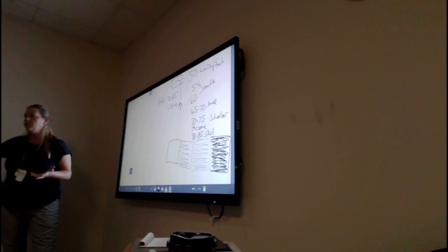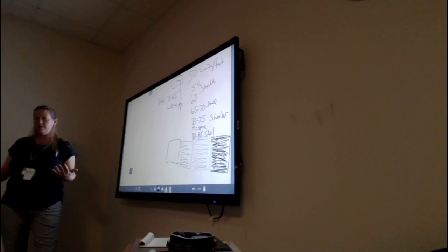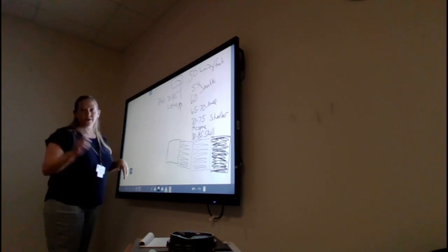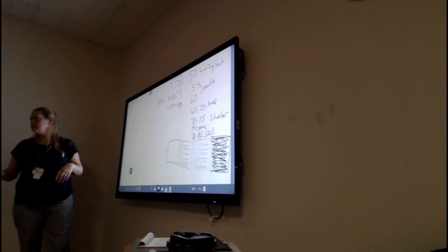So the only thing you really have to know that is different from all of this is your kVps. The chests are 110 to 125. That's the different one.